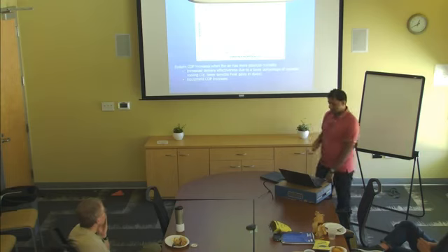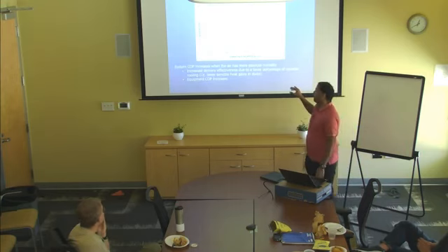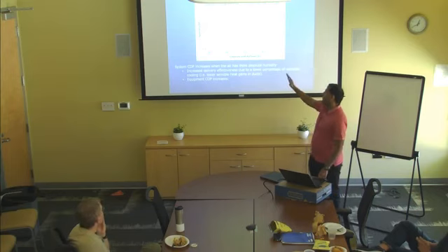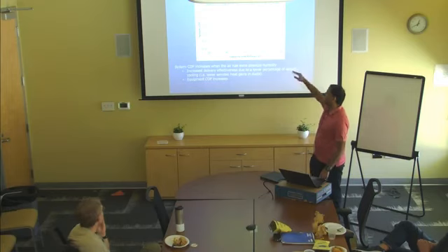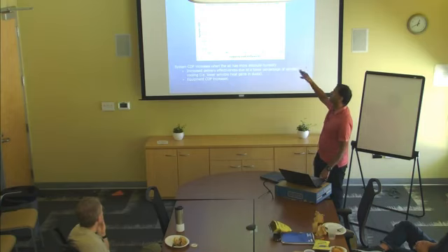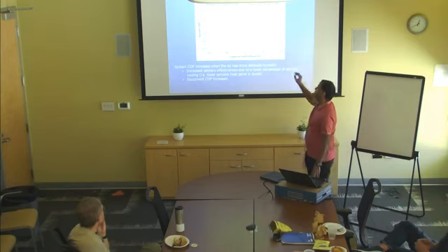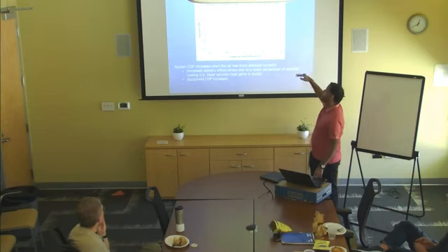The next set of results in this category is trying to do the same capacity and airflow variation synced tests, but at different indoor conditions. So the blue line is a dry indoor condition, whereas the red line is a wet, 80-67 condition. You can see that the system COP actually increases for the wet case.